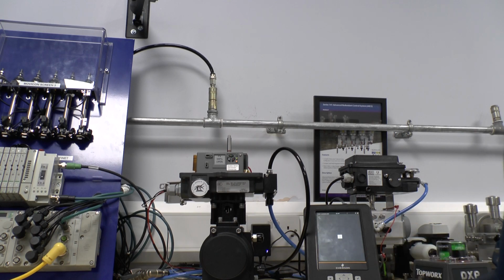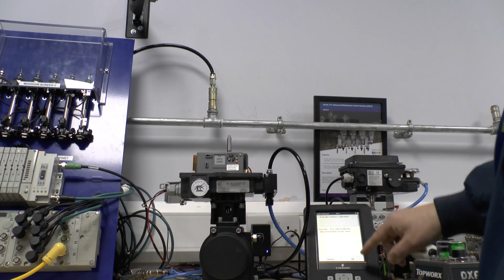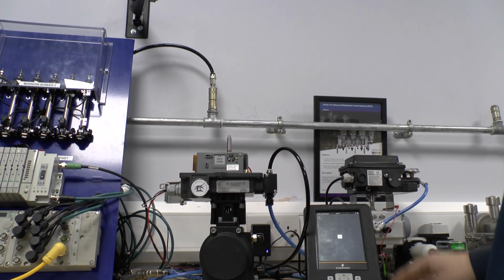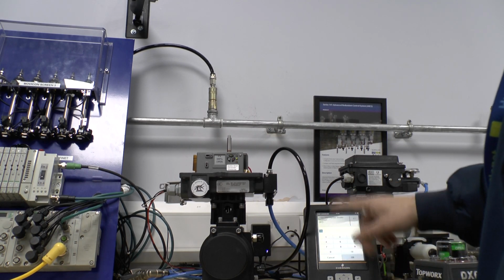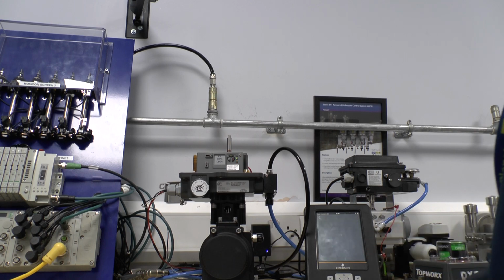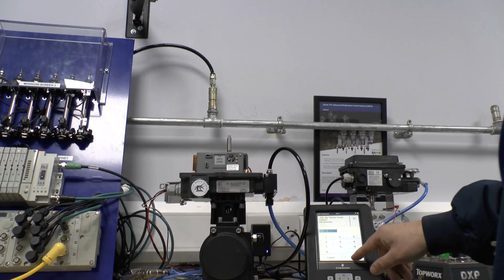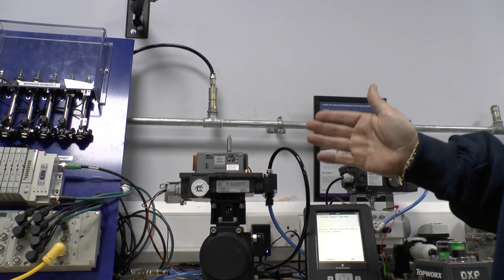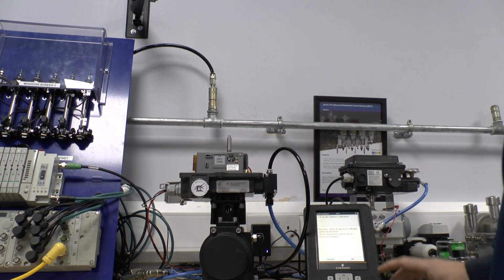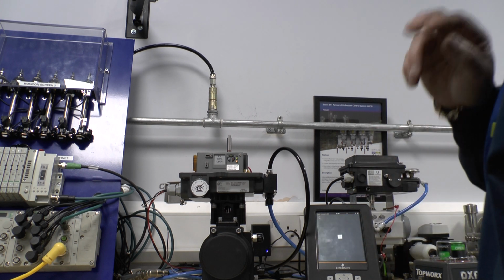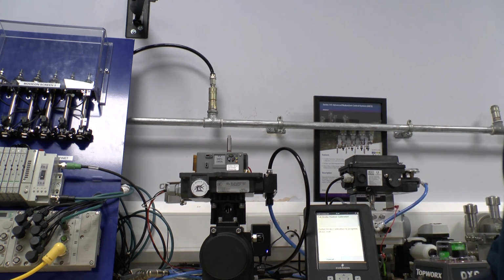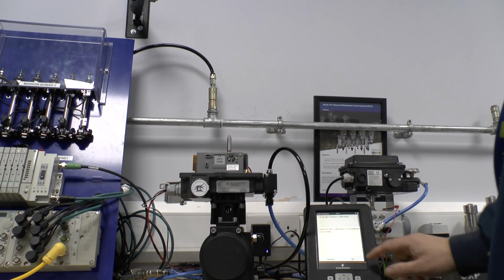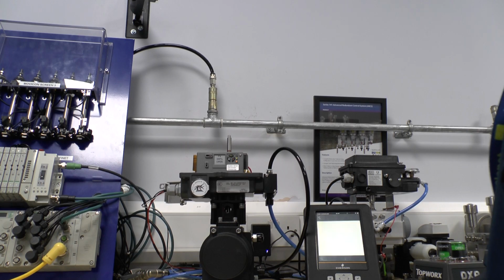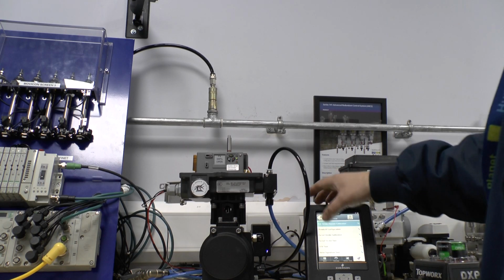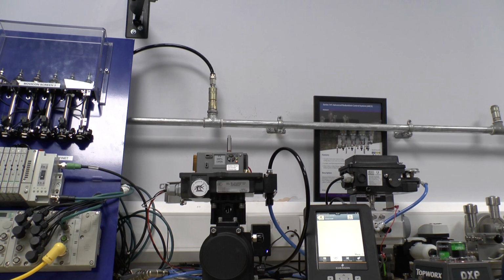Partial stroke calibration - this device asks you to do it through the menu, but on here we'll do 87 with a 20% tolerance, and the timeout of 10 seconds. That means if it hasn't reached the point within 10 seconds, it will create an alarm. You can obviously change that time if that's significant. So it goes through the partial stroke calibration, and that is now fully set up and fully configured.